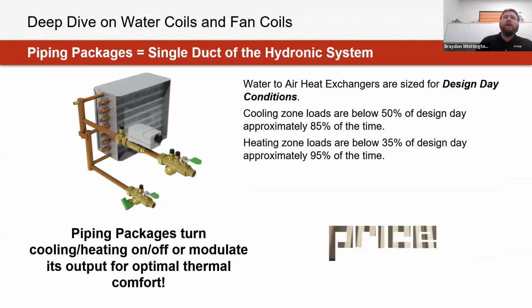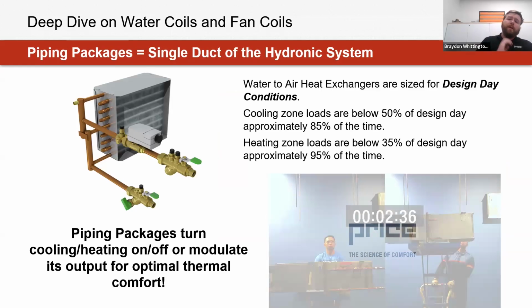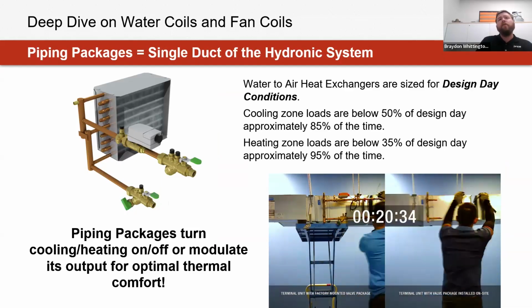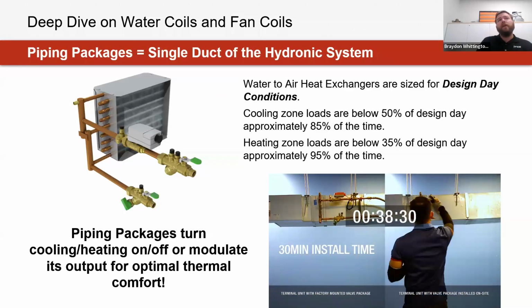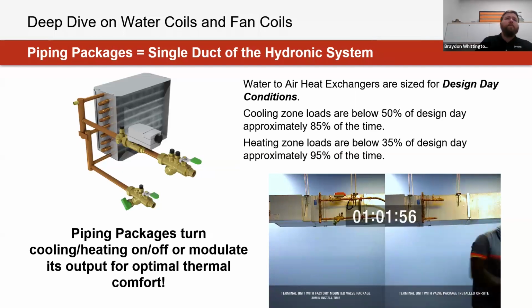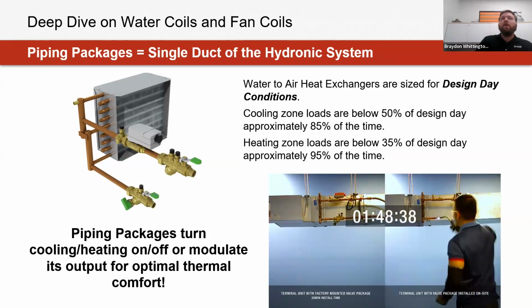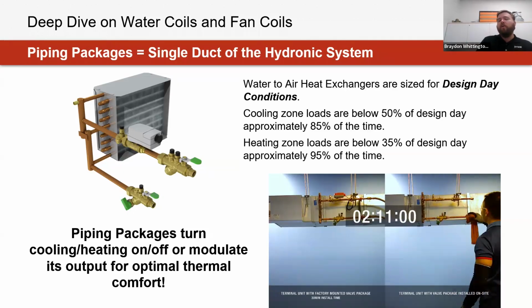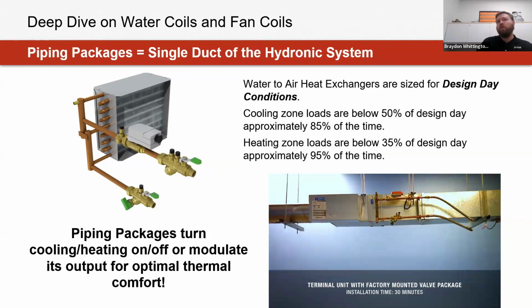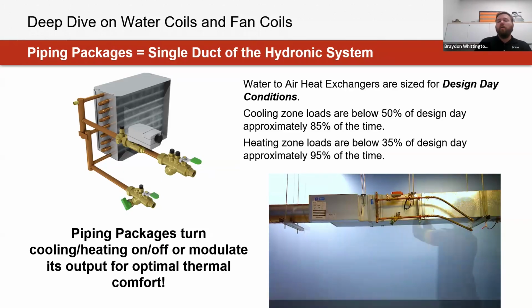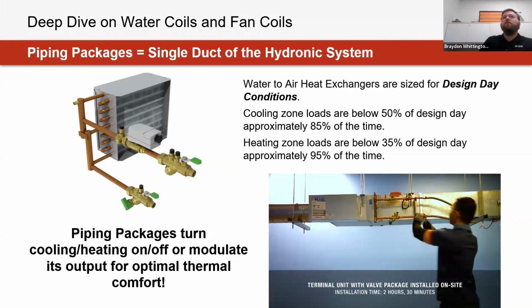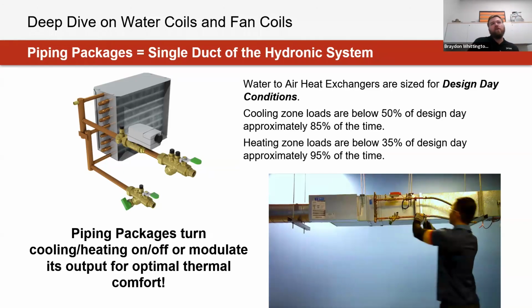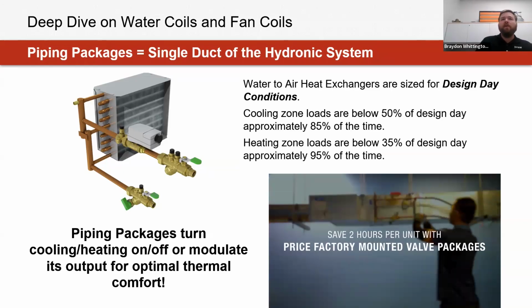And with that, in terms of customization and where that also comes into play, we'll briefly go through this too, because I want to be cognizant of time for this water coil portion that I really wanted to get into the example. So this also opens up different custom solutions that can be paired with this equipment. Commonly, just because you're not always operating at design day conditions, you'd see different valves and components to modulate the fluid flow through that equipment, so there's also the option for valve packs or piping packages that can be paired with this equipment.